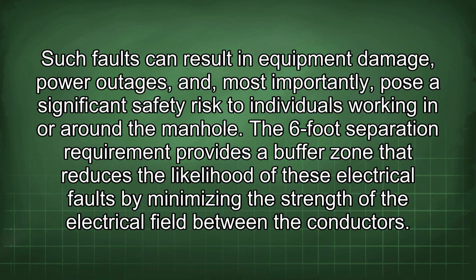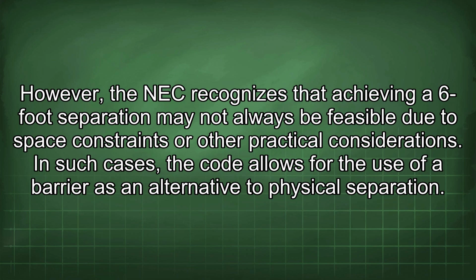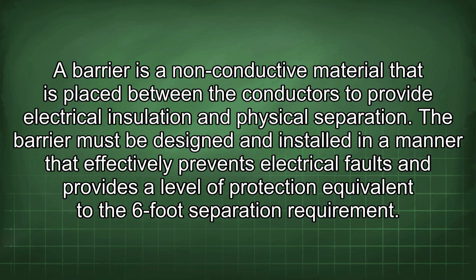The 6-foot separation requirement provides a buffer zone that reduces the likelihood of these electrical faults by minimizing the strength of the electrical field between the conductors. However, the NEC recognizes that achieving 6-foot separation may not always be feasible due to space constraints or other practical considerations. In such cases, the code allows for the use of a barrier as an alternative to physical separation. A barrier is a non-conductive material that is placed between the conductors to provide electrical insulation and physical separation. The barrier must be designed and installed in a manner that effectively prevents electrical faults and provides a level of protection equivalent to the 6-foot separation requirement.